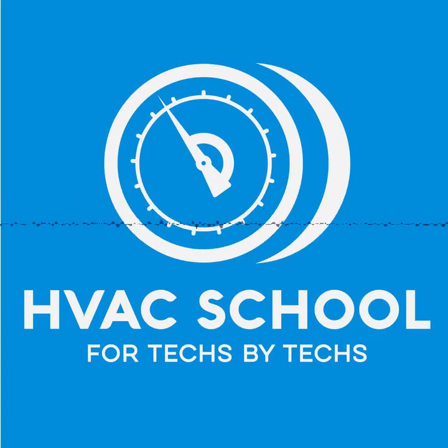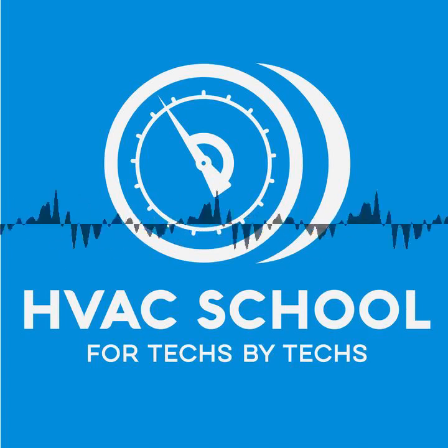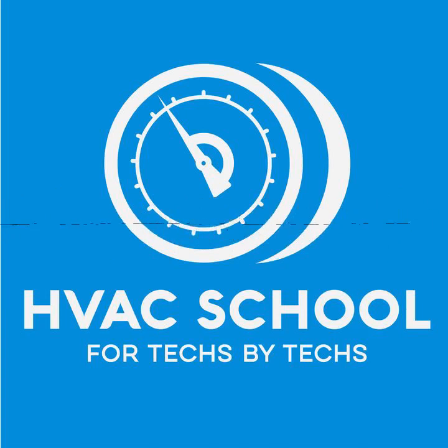Now, here's the other thing. The nitrogen is the gas that your vacuum gauge is calibrated for. Anybody that's using a thermistor style vacuum gauge, which would be JB, Testo, Robinair, Thermal, BlueVac, pick any manufacturer you want, they use thermistor vacuum gauges. There's nobody that's using an absolute pressure sensor of any kind for measuring vacuums at the levels we do because they're just not accurate enough. There's some, like Testo, I believe, uses a Pirani sensor.